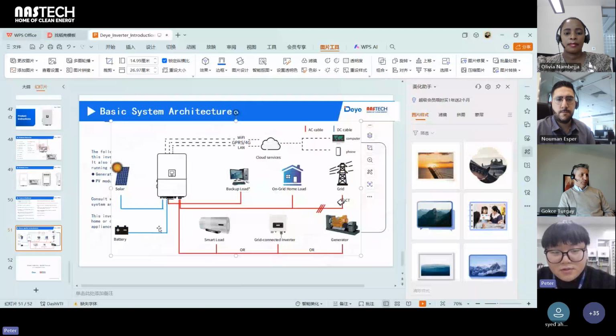There is a backup load. It will be connected to our load port. When the grid is off, the home load connected on the grid side will be turned off, but the load on the load port can continue to work, and the switching gap is only 10 milliseconds for the three-phase inverter. So loads like a computer or lights can work normally without any stop. But for inductive loads, we need to let the inductive load stop and then restart again, because if we use it as a UPS, the inductive load might be damaged because of the frequency change.